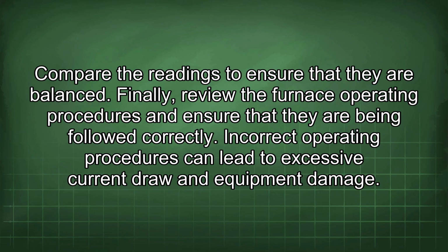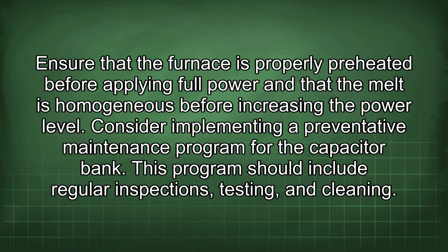Finally, review the furnace operating procedures and ensure that they are being followed correctly. Incorrect operating procedures can lead to excessive current draw and equipment damage. Ensure that the furnace is properly preheated before applying full power and that the melt is homogeneous before increasing the power level. Consider implementing a preventative maintenance program for the capacitor bank.